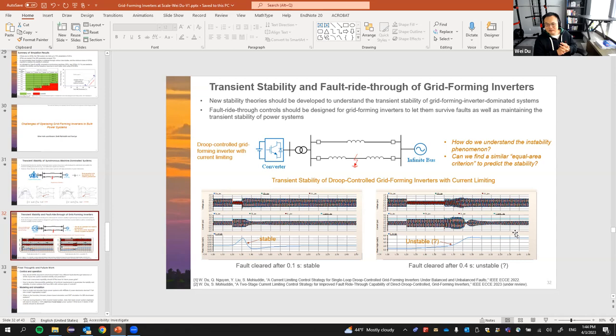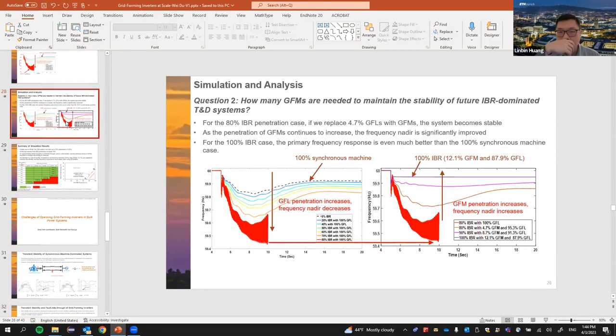Yeah. Okay. Thanks. Because I see in your slides, like slide 28 or something, when you have a lot of droop converters, then basically the frequency just goes from one steady state to another steady state. So you really don't feel the inertia. Right, the frequency deviation is already very small. So I was very curious whether we really need inertia, because people now are talking about low inertia systems a lot. But perhaps instead of adding inertia, adding some droop effect would be enough for that.